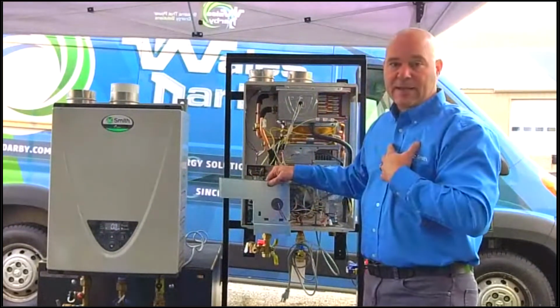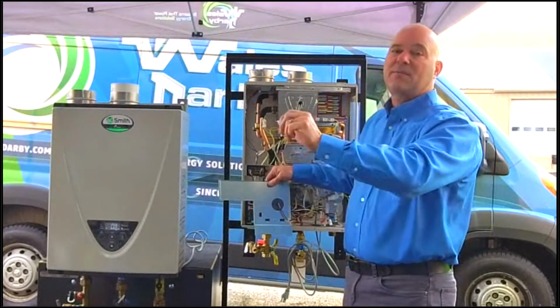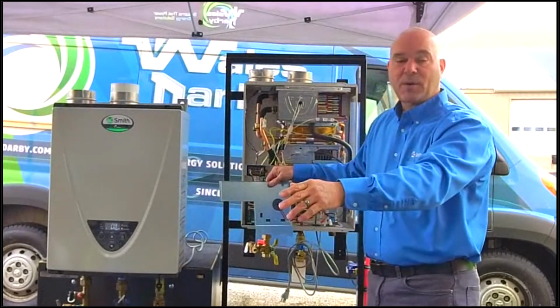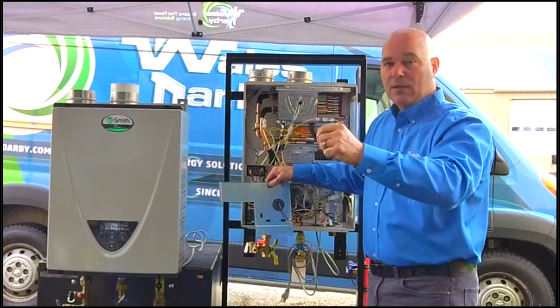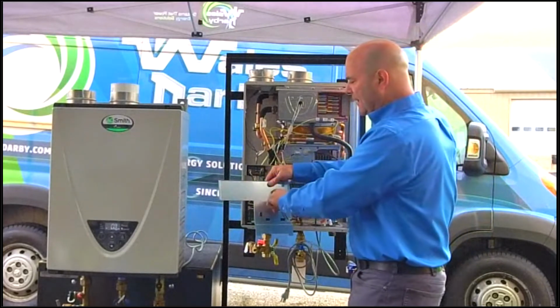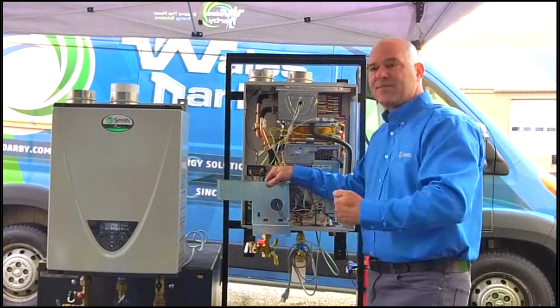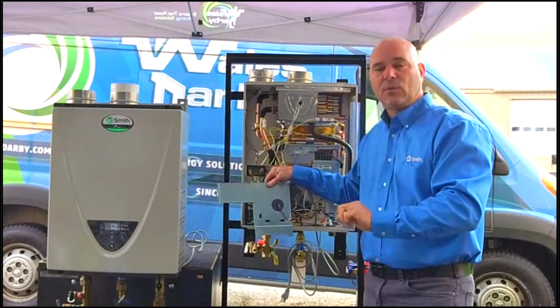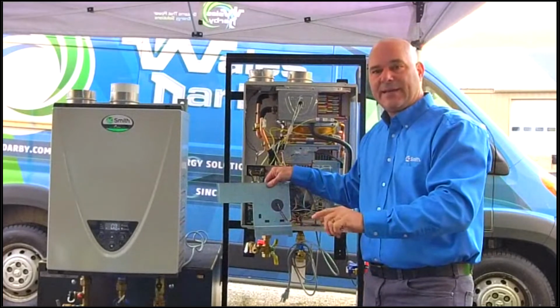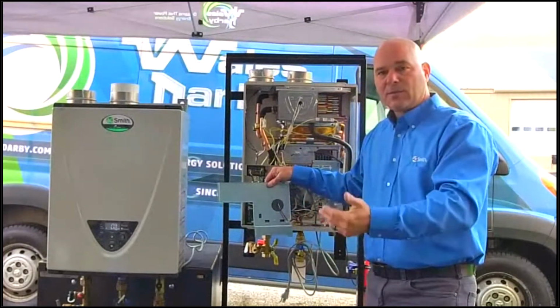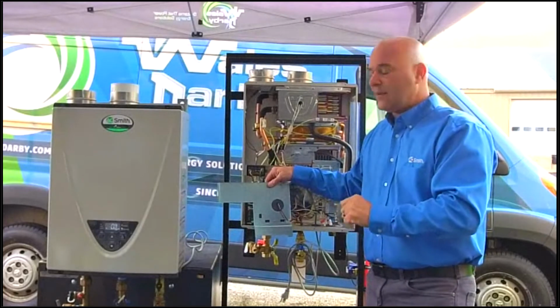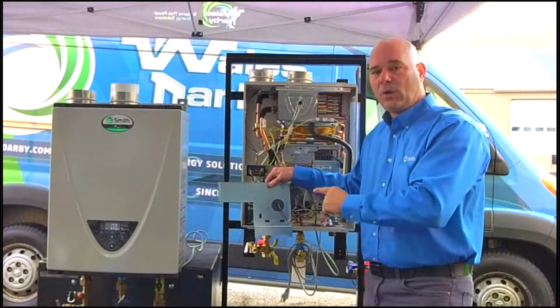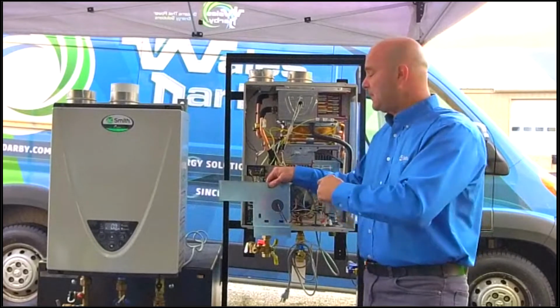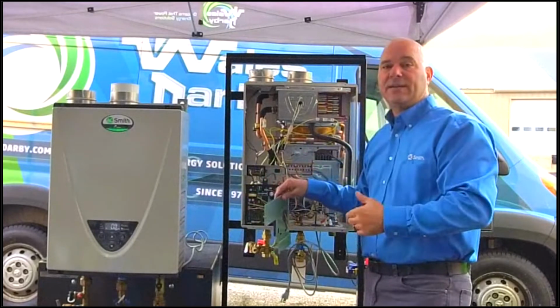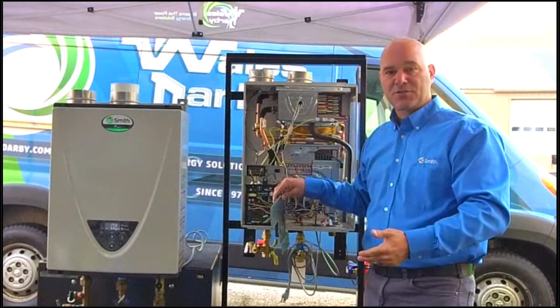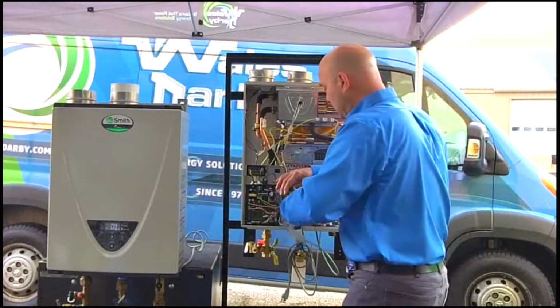If I'm the next guy that comes in behind you and you got the product preserver and I'm there to do a service, I'm going to change out the product preserver cartridge. I'm going to take and look at the back of this controller and see what that initial install looked like, what the test was. And based on that test and the gallons that you put on there, I'm going to run that same test. And if I'm a half a gallon below what your test was, that tells me that somewhere in here on the water side, I'm dirty and it needs to be flushed. Okay, so use this as a tool.